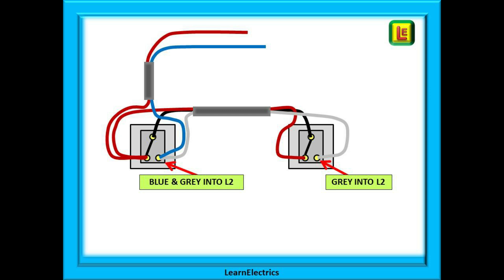At the first switch you should have just two colored wires left, a blue and a grey. Put these together into terminal L2. At the second switch, put the only remaining wire, the grey wire, into terminal L2.